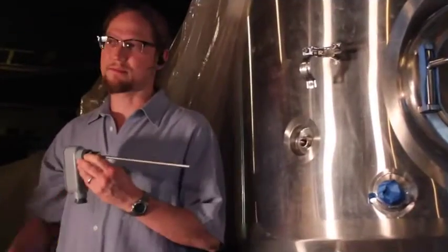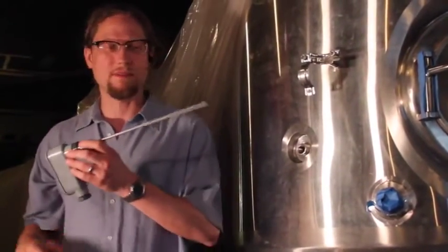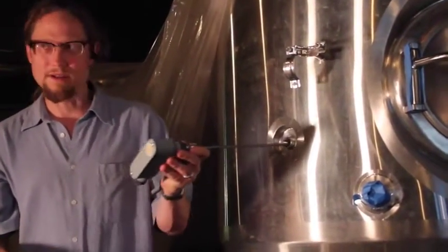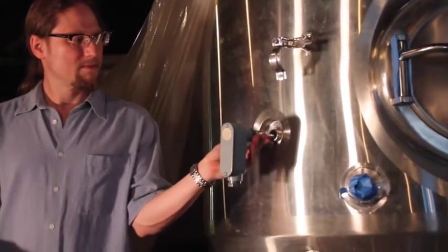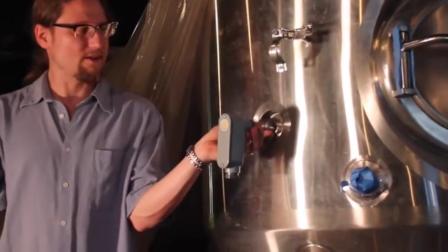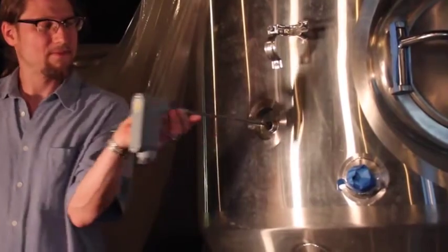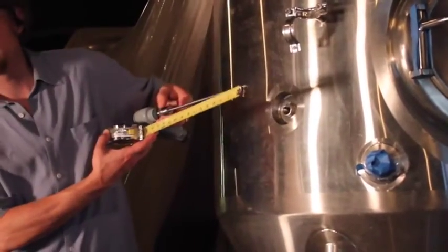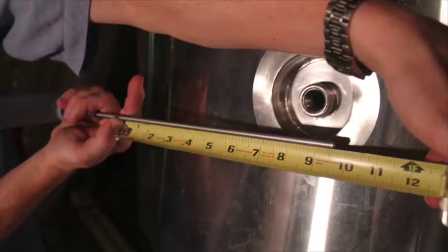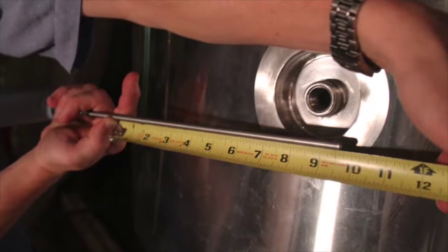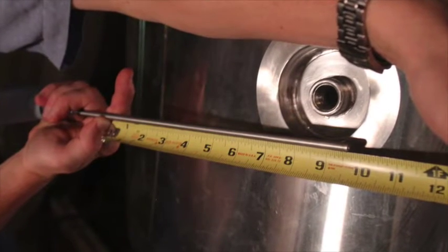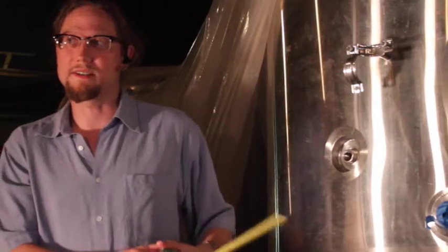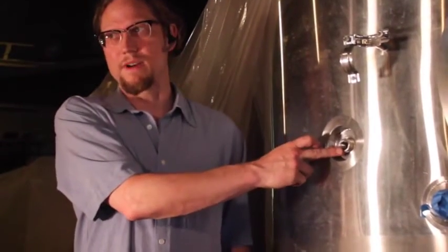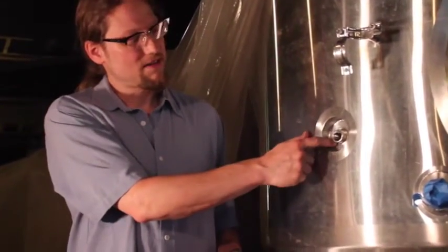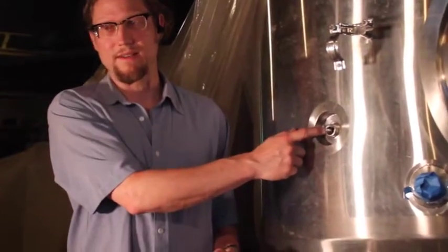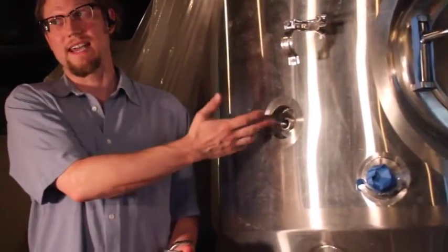So here I have a temperature probe that happens to be 12 inches. So I'll stick this into the thermowell. And I'll mark the end with my finger. You could use a pen or something. Take it out and measure it. And here you can see it measures about 9.5 inches, which happens to be the length of a standard thermowell, 9 inches, plus a half-inch coupler that they've welded on. Well, this is really a 9.5 inch.